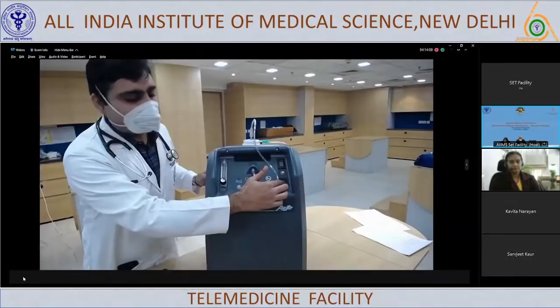What we see here is a flow meter. Here it is from 1 to 5 liters per minute. Some machines can go up to 10 liters per minute also. This is the outlet for the oxygen. This is a reset button, and this displays the hours for which the machine has been used.